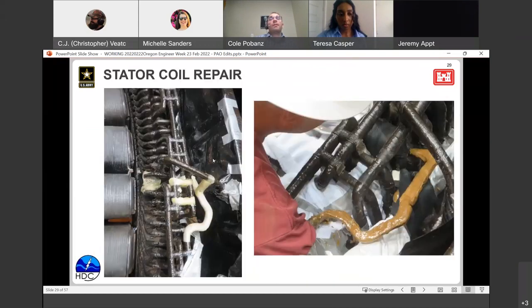When we replace a coil, we're not really replacing it, we're bypassing it with a jumper. In the picture on the left, you can see where the coil failed - we don't have a picture of the exact failure point, but near the bottom and middle you can see where we took that coil connector. This is just a bar of metal cable that jumpers over that coil, essentially taking it out of the system, so the generator operates with one less coil. The picture on the right shows the failed coil's connection.